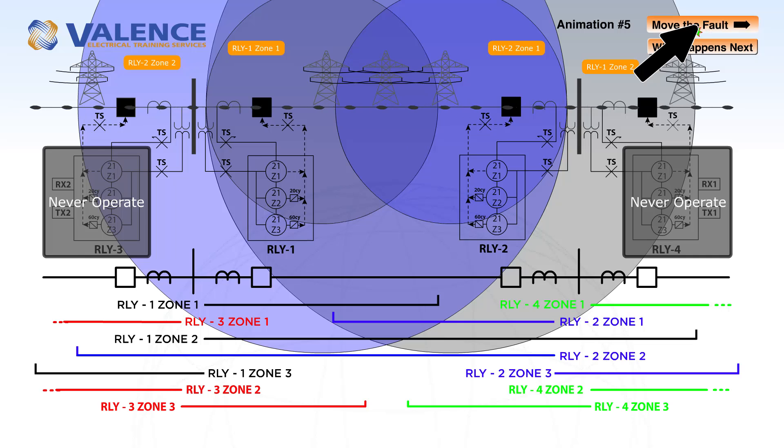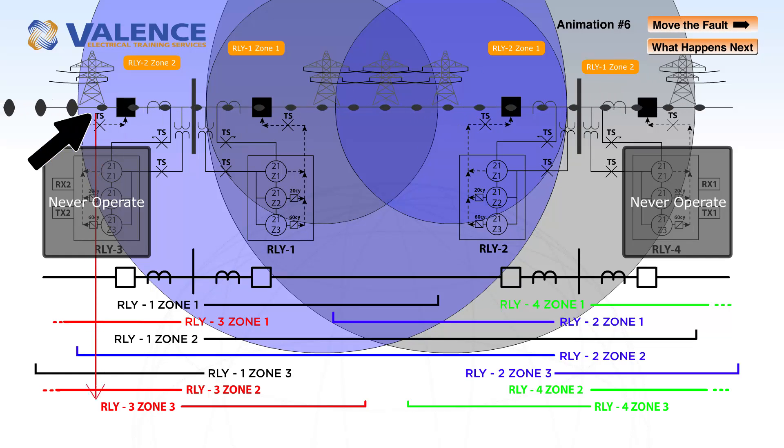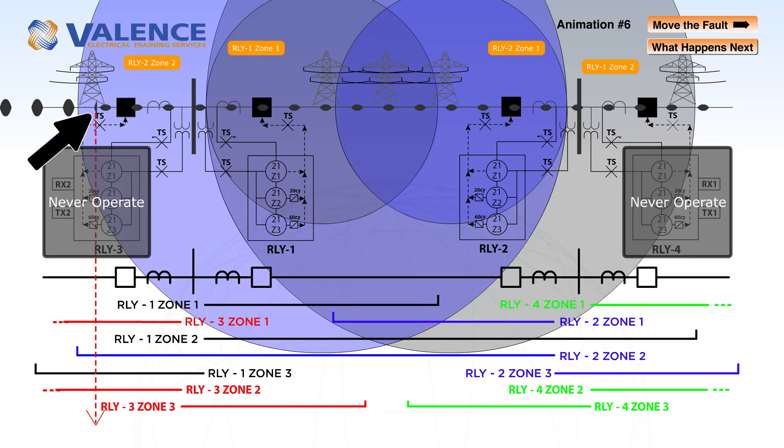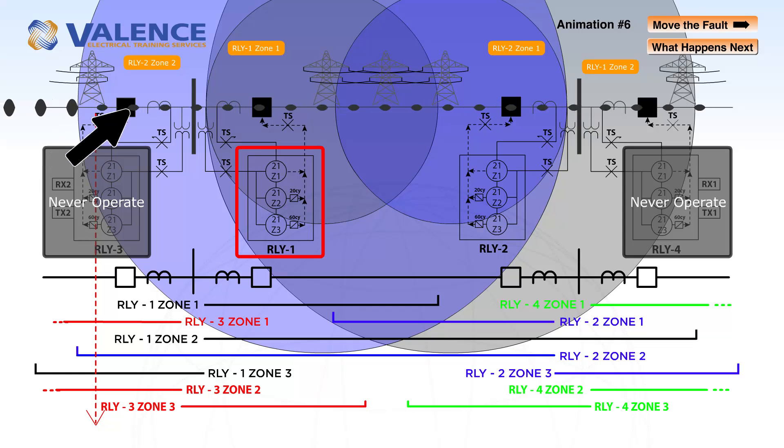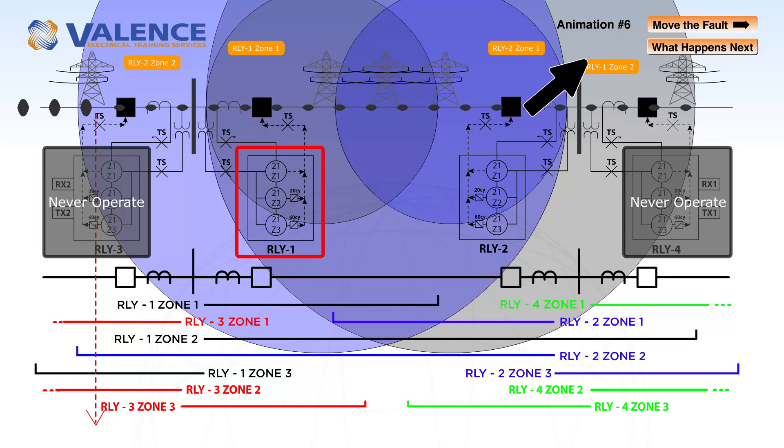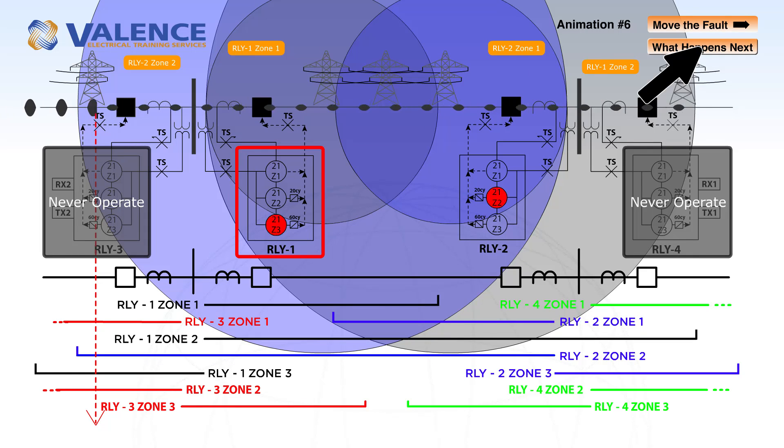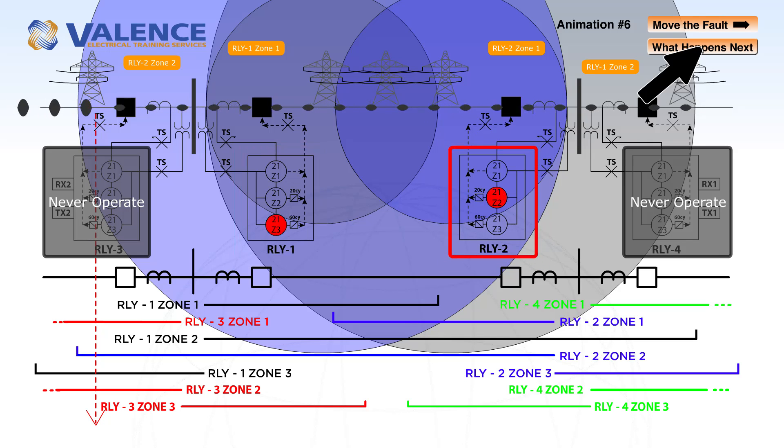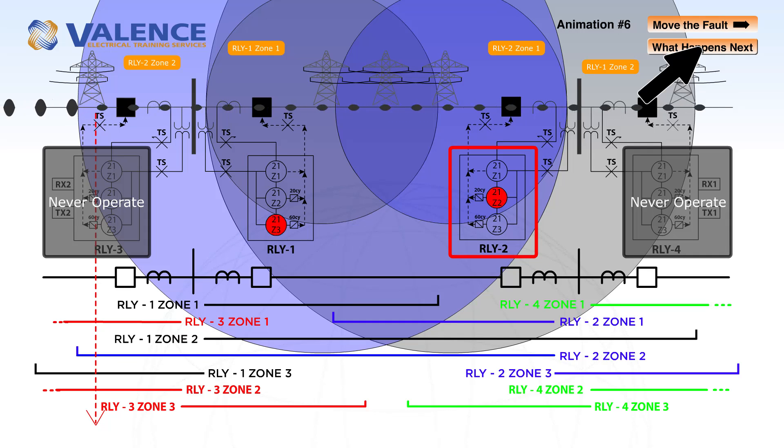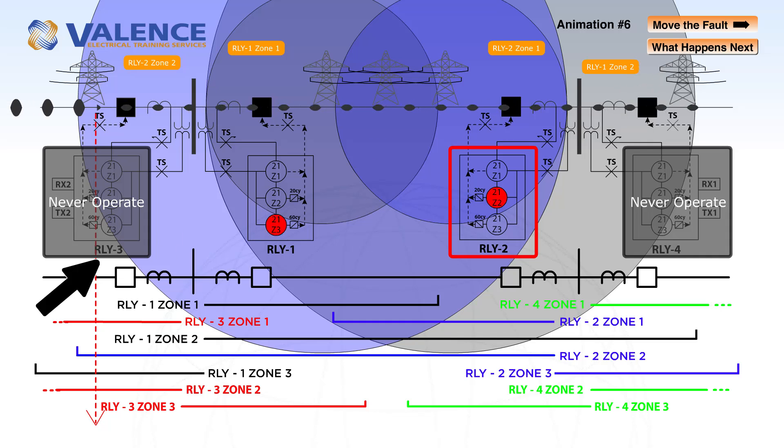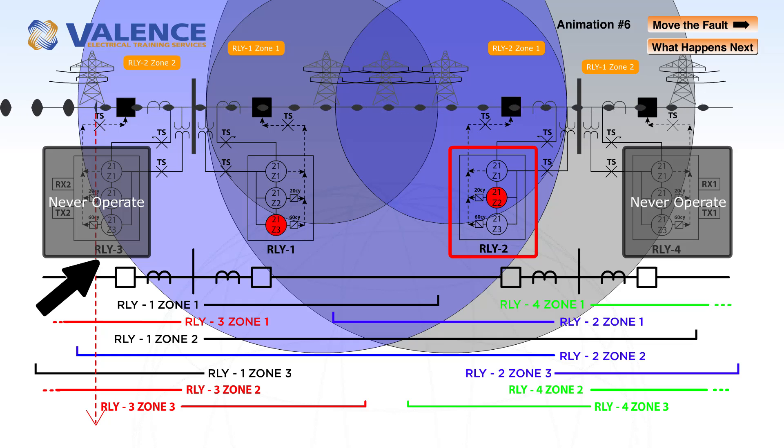So let's see what happens when we move the fault outside of the line. This fault occurs behind relay 1, so relay 1 will detect a zone 3 fault because the fault is behind it. Relay 2 is going to detect a zone 2 fault because we're still within zone 2 for relay 2. Relay 3 is disabled, so it's not going to operate at all.